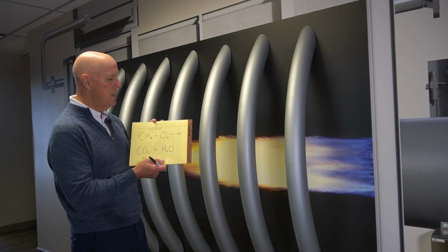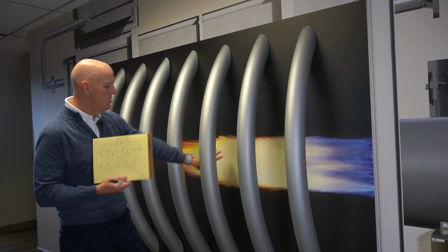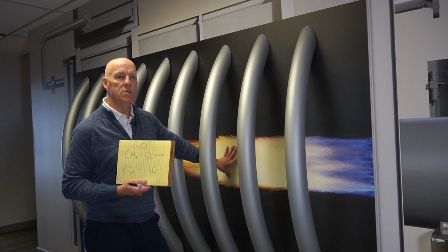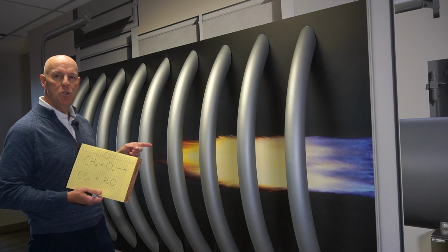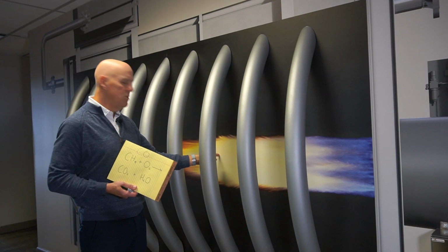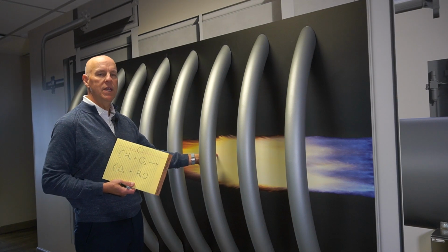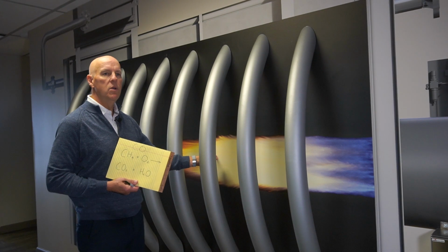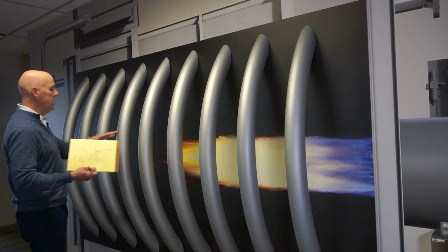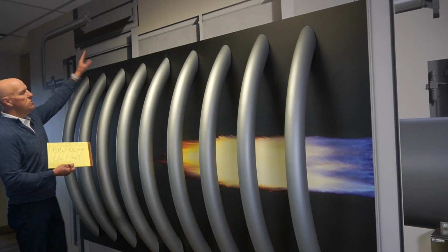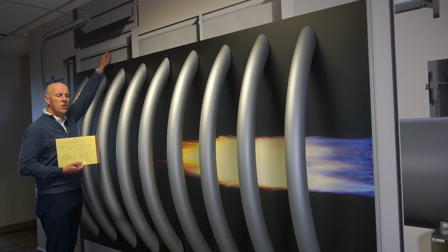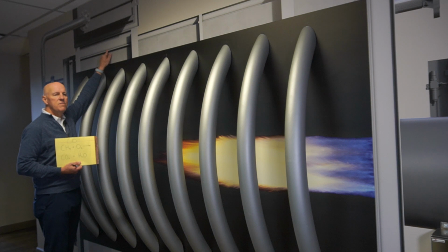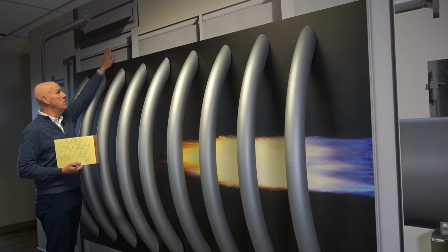So in the process of doing that, there's CO present in large amounts in the flame. In fact, if I were to take a high temperature probe and go in and see what the gases were at this location, there'd be a lot of CO. Well, what happens though is magically, as it goes through the convection section and exits the stack, there's almost no CO. In fact, a lot of times it's not even at detectable levels at a ppm level.